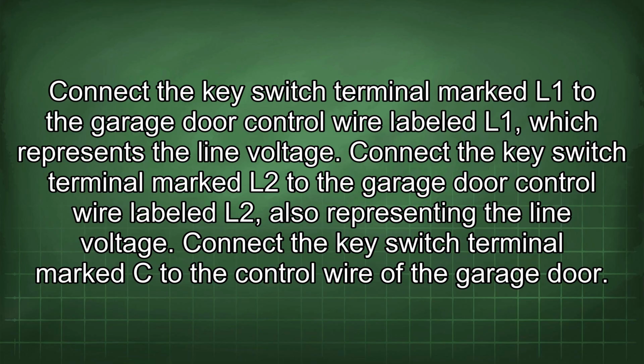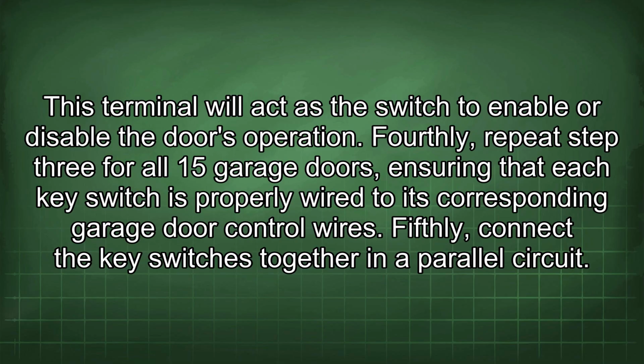Connect the key switch terminal marked L1 to the garage door control wire labeled L1, which represents the line voltage. Connect the key switch terminal marked L2 to the garage door control wire labeled L2, also representing the line voltage. Connect the key switch terminal marked C to the control wire of the garage door. This terminal will act as a switch to enable or disable the door's operation.